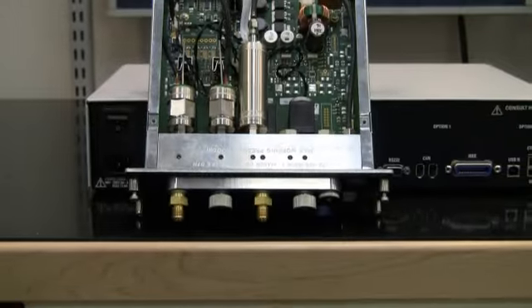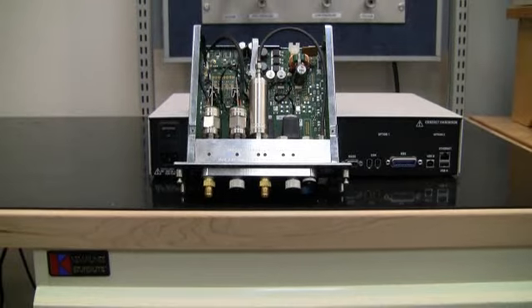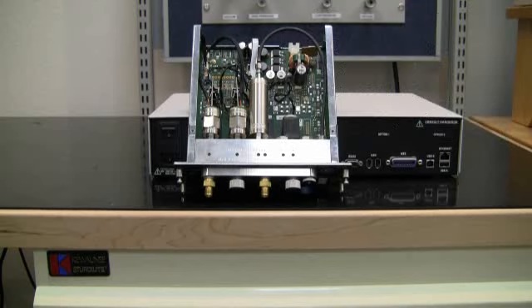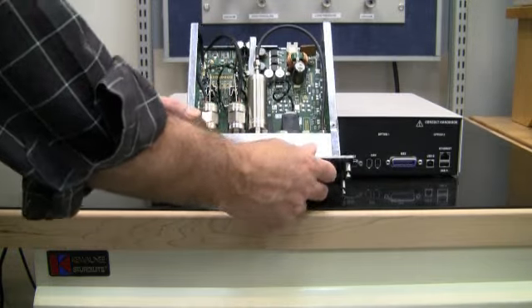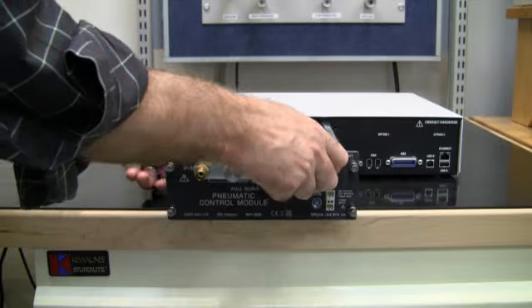Since the pulse width modulated control valves are matched to the specific control module pressure range, optimal pressure control speed and stability is assured when changing control module ranges. A variety of control module ranges are available from as low as 10 inches of water full scale, or 25 millibar, to as high as 3000 psi full scale, or 210 bar, providing maximum flexibility and rangeability in a single PACE5000. To install the control module, simply slide it into the chassis and tighten the 4 retaining screws.